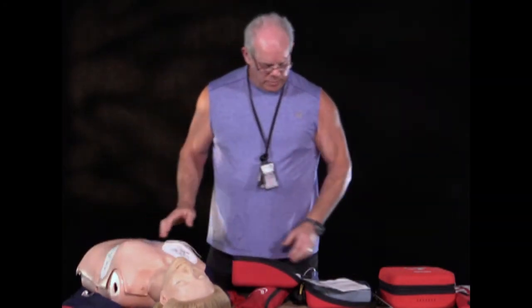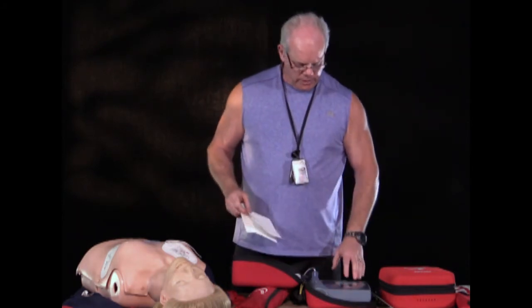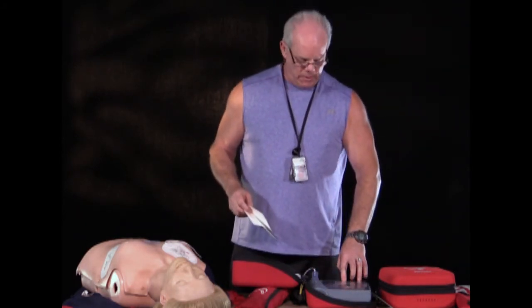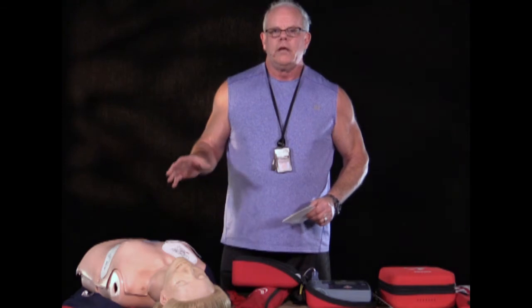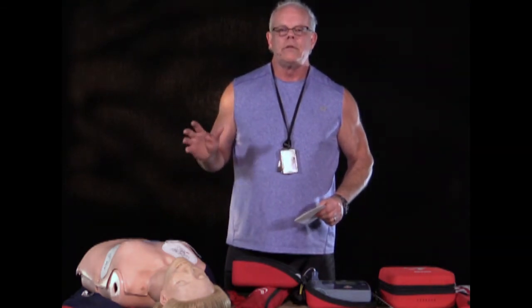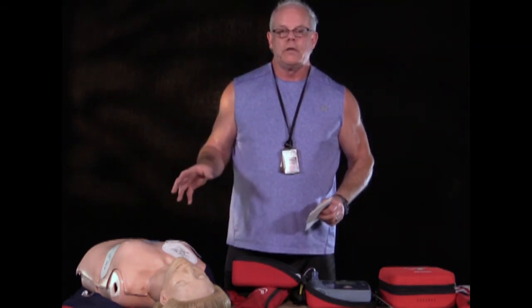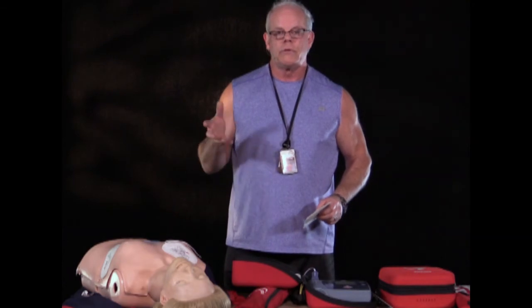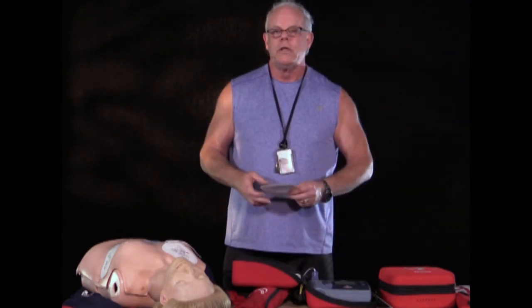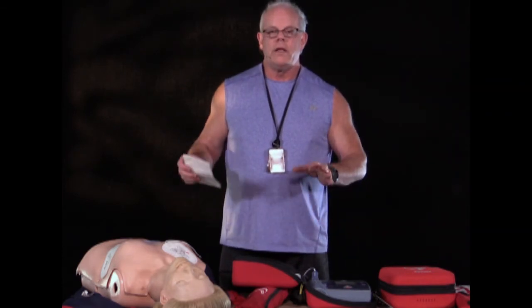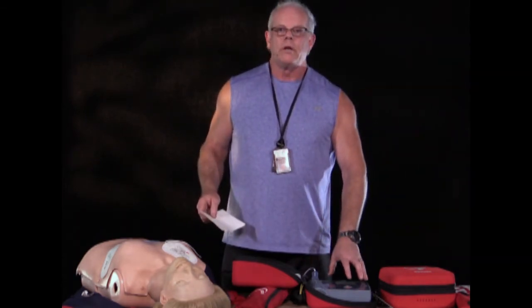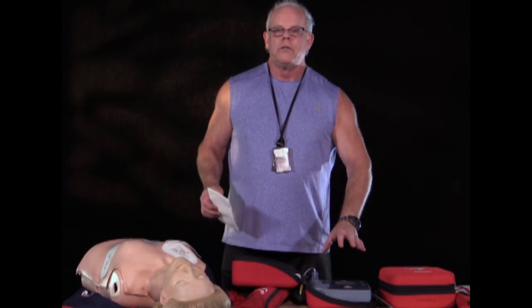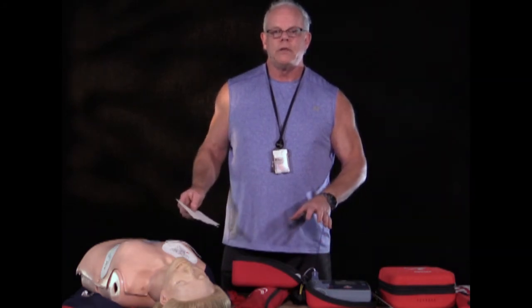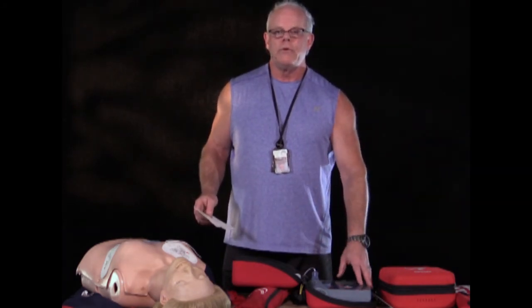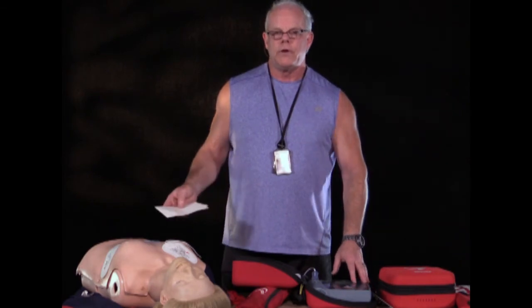And then once the pads are on and the defibrillator can read, I'm turning off the defibrillator now, so once the pads are on, it will read the signal. If it's a cardiac arrest situation where the ventricles are fibrillating, there's a unique electrical signal that the AEDs will read. And if the person is shockable, the defibrillator will come on in a moment and say, charging, please stand back from patient, and then the orange button will light up and it will give you a command to push that button to provide the shock.